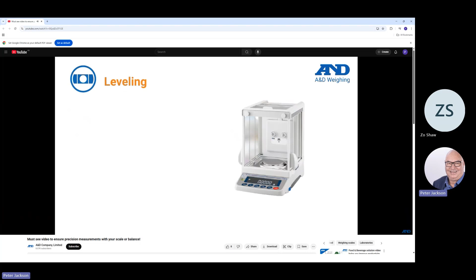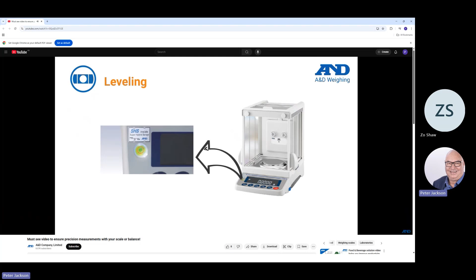The balance must be leveled prior to weighing. Check the level indicator before each use, and adjust the leveling feet if needed. Most A&D models offer illuminated spirit bubbles, allowing for easier viewing and setup.